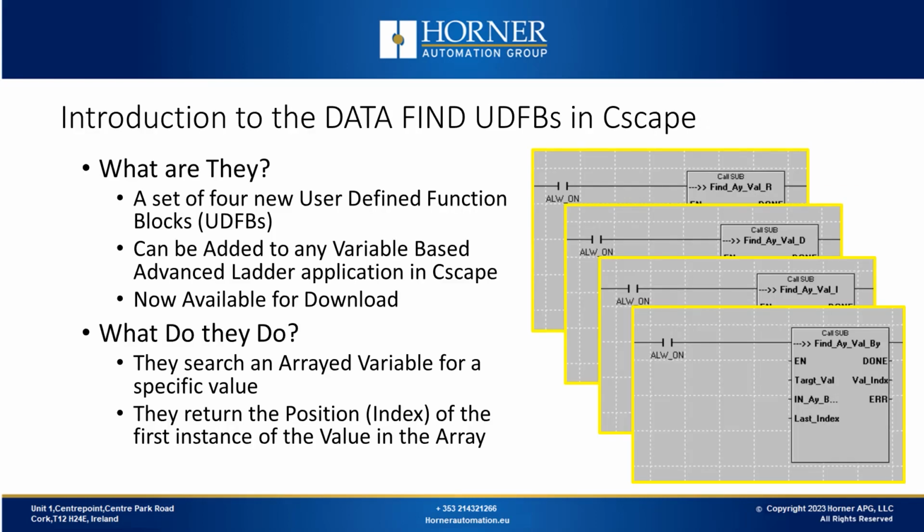Firstly, as user-defined function blocks, there are a set of 4 new UDFBs that you can add to any variable-based advanced ladder application in Cscape and that are also available for download. They allow you to search for a specific value in an arrayed variable. So if you have a very large array, maybe with 1000 different elements in it, and there's a specific value that you're looking for somewhere in that array, these user-defined function blocks will return the exact position of the first instance of the value you're looking for, in terms of where it is in the array.